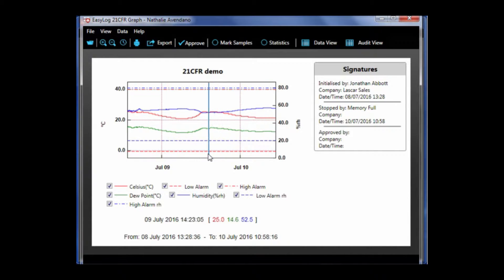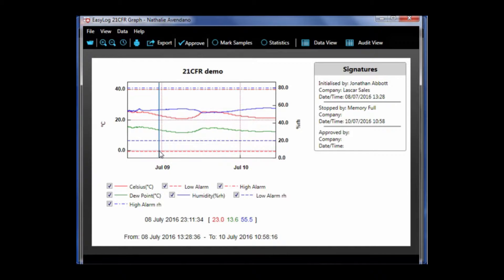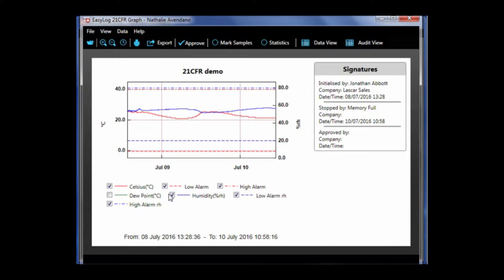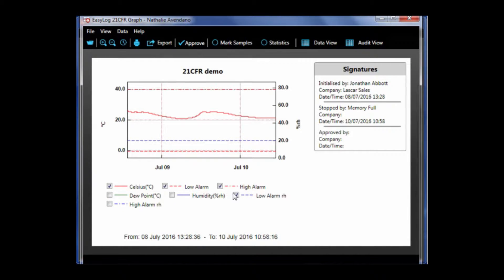If you notice, as I hover over the data points, the numerical reading of those are shown at the bottom of the screen. You are able to turn off different traces, so I'm just going to turn off the humidity and the dew point trace, as well as their associated alarms, and just be left with temperature.